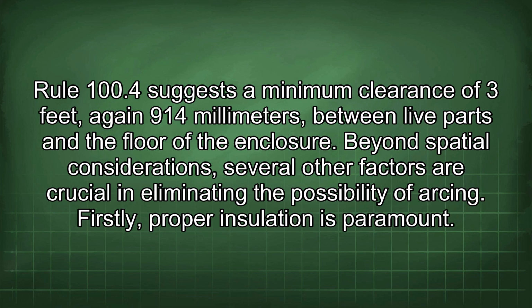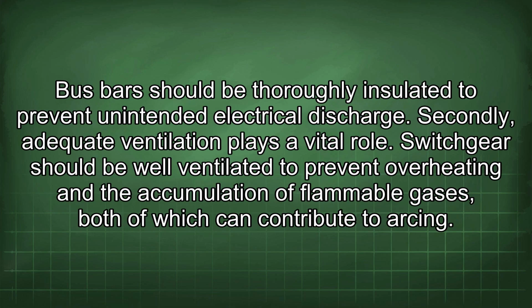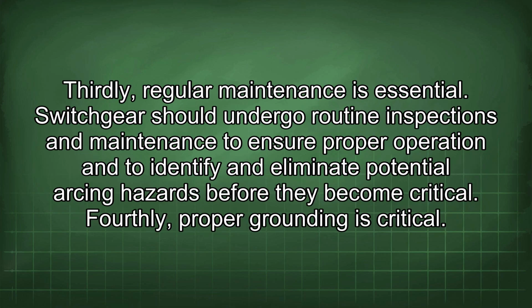floor of the enclosure. Beyond spatial considerations, several other factors are crucial in eliminating the possibility of arcing. Firstly, proper insulation is paramount. Bus bars should be thoroughly insulated to prevent unintended electrical discharge. Secondly, adequate ventilation plays a vital role. Switchgear should be well ventilated to prevent overheating and the accumulation of flammable gases, both of which can contribute to arcing. Thirdly, regular maintenance is essential.